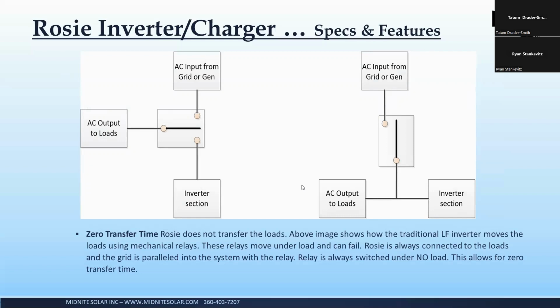where if you've got a huge load, if you look at the example on the left, your box on the very left is your loads. Then up at the top is your grid, and at the bottom is your inverter. So when the grid is present, that relay actually moves the arm over and connects the loads directly to the grid, disconnects from the inverter. So there's an arc on the relay there, and then it connects to the grid, and there's another arc there, because it's all under load.